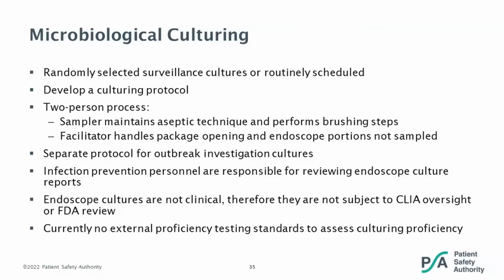It is a two-person process. There's just no way around it. When you're obtaining samples, you need to maintain an aseptic technique and perform brushing steps. That's for the person that's collecting the specimen. The person that's assisting you is going to handle package opening and endoscope portions that are not sampled. And then you need to have a separate protocol for outbreak investigation cultures. So if you do have an event within your organization where there's a potential outbreak, then there needs to be that separate protocol. Infection prevention personnel are responsible for reviewing endoscope culture reports.